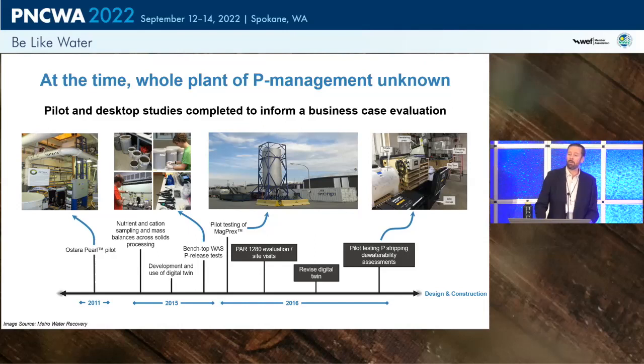MAGPREX — at the time called AIRPREX — was on the scene and was piloted. Our project, PAR 1280, got involved: we upgraded the digital twin model and set up pilot digesters — one control and one with WAS-phosphorus stripping — measuring dewaterability with real data, and plugging those results into our economic model.